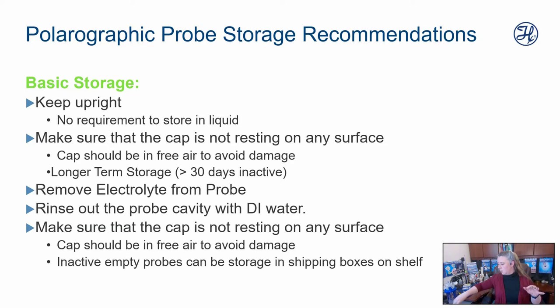You want to store these upright if at all possible. And if you're not going to use them for at least 30 days, then you want to remove the liquid in them and store them dry. And then before you use them, you'll want to add the liquid and do the same maintenance thing. So you'll want to rinse them off. You'll want to polish the cap. You'll want to add new liquid. You'll want to verify that their voltage is between 40 and 80 nanoamps, and then you'll want to polarize them.